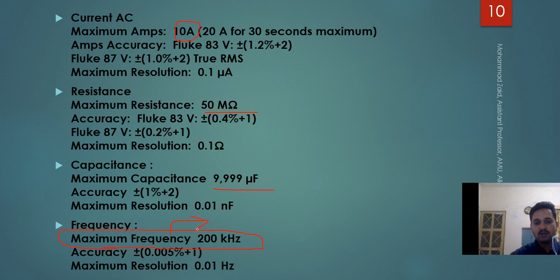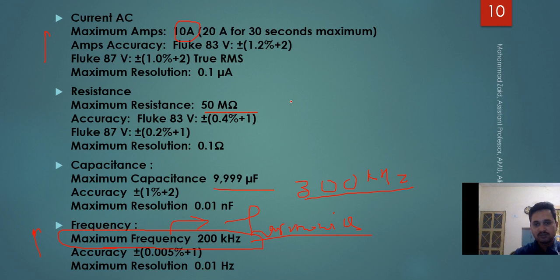So if it can give you the readings up to 200 kilohertz, it depends on your applications, up to which you want. Suppose in some applications the maximum frequency which should be measured is 300 kilohertz and so on, then you have to choose a different equipment or a different make. Same equipment but of higher frequency rating. Similarly, the maximum current rating can also go up, then maximum voltage rating can also go up. So it depends, and depending upon that you need to choose. So this is an example of how you can choose equipment.